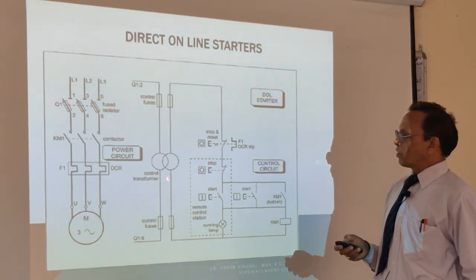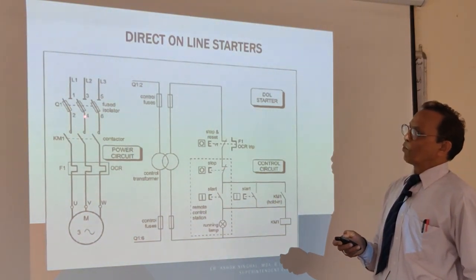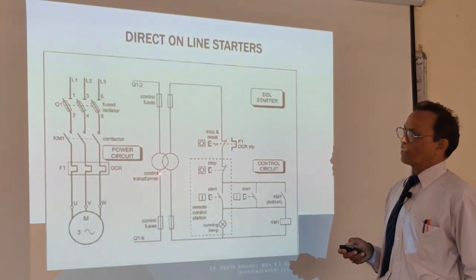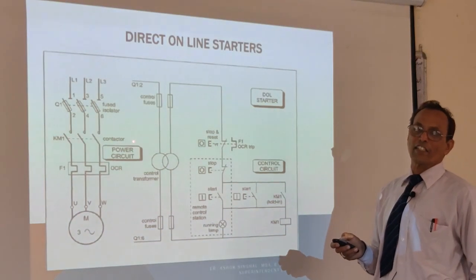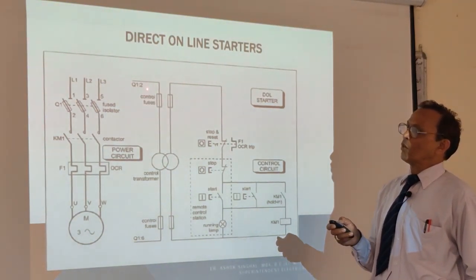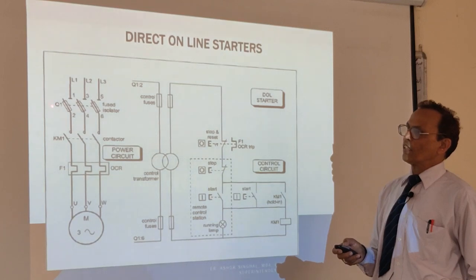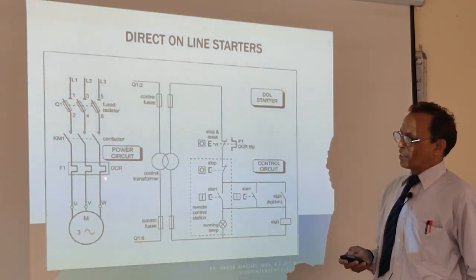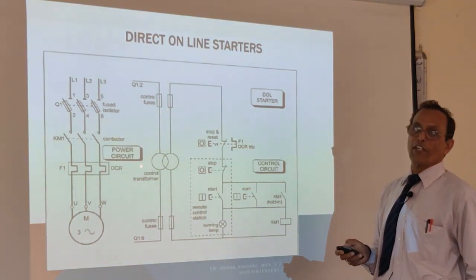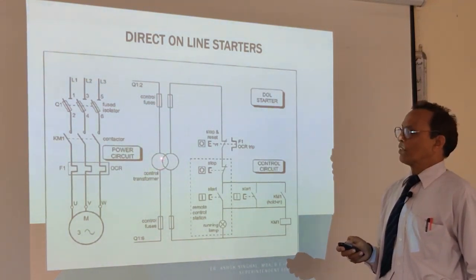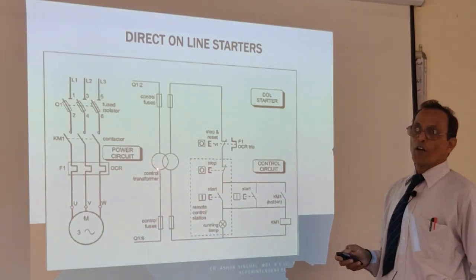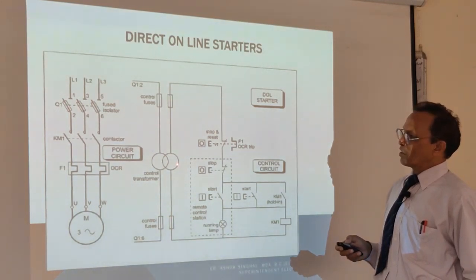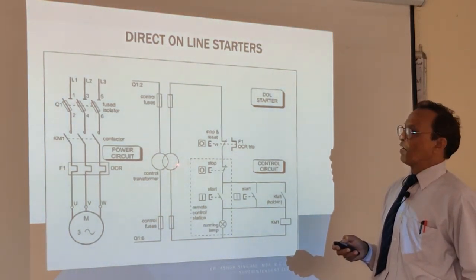This is your control circuit. The 440 volts comes from here to the step-down transformer. When tracing the electrical circuit diagram, Q12 means Q1 of this breaker — line 2 comes here, and Q16 comes to this point. This means 440 volts is available to the step-down transformer, which steps it down to 220 volts.